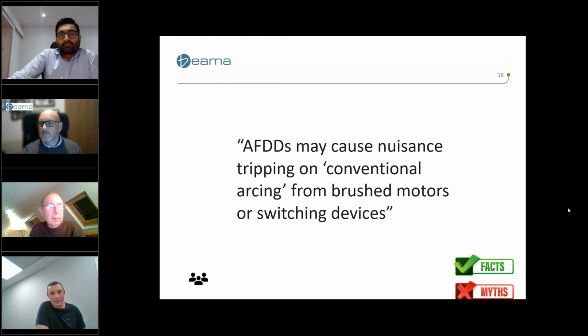As the guys have said, there were specific tests for common loads that would be protected by an AFDD. It's also worth mentioning there's a range of EMC tests the product has to undertake, to ensure they're not affected by normal phenomena of the system, so any signals or disturbances don't operate AFDDs when they shouldn't.